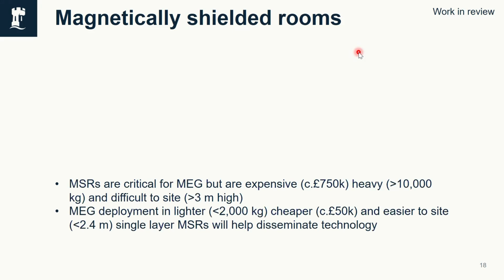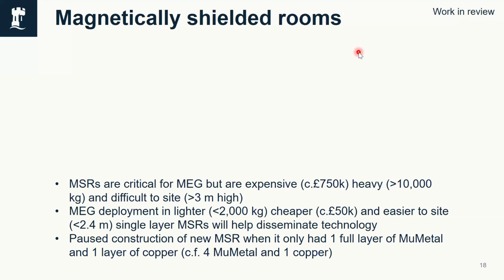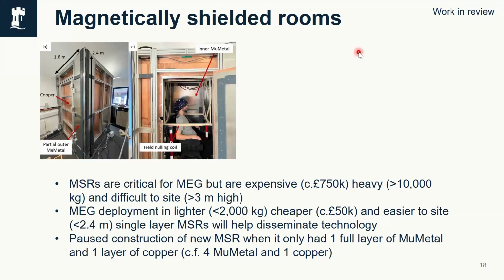If we could start to deploy MEG and take advantage of the cryogen-free nature of OPMs, if we could start to deploy these systems in lighter, cheaper, easier to site MSRs, that would be really useful for dissemination of the technology. We were building a new MSR in Nottingham, and we paused the construction when it only had one layer of mu metal and one layer of copper. So it looks something like this. There's a little bit of the outer mu, but it's not a complete shell, and you can kind of see the copper and then the inner mu metal. And then this wooden structure here is just a triaxial Helmholtz coil to back off the remaining field.